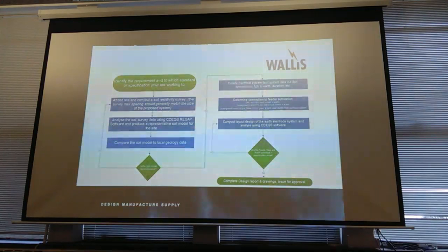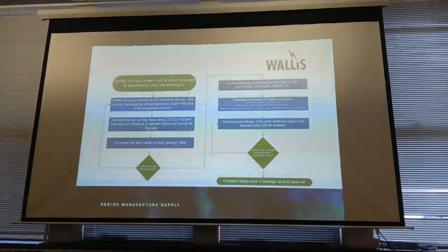Again, the soil resistivity survey is only as good as the measurements you're gaining. If they're being fouled by something, buried services, overhead lines that are inducing stray currents onto your test leads, it will affect the readings. So if you've got a geology map, it's always good practice to have a look at the geology map, compare it to the tables in the British Standard, because they give you some probable values for different geologies, and then compare it to your readings as well. At least it's a three-way check then.